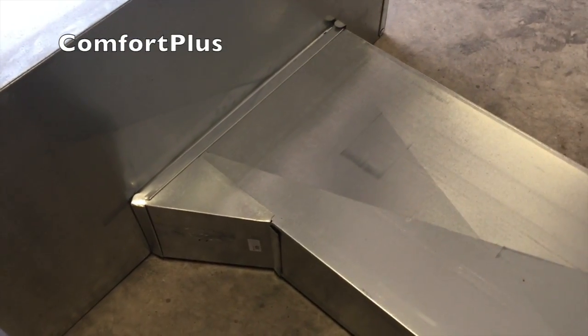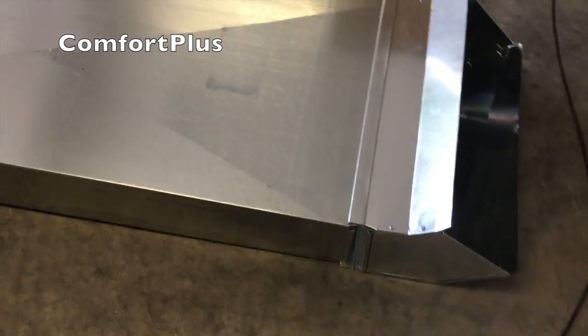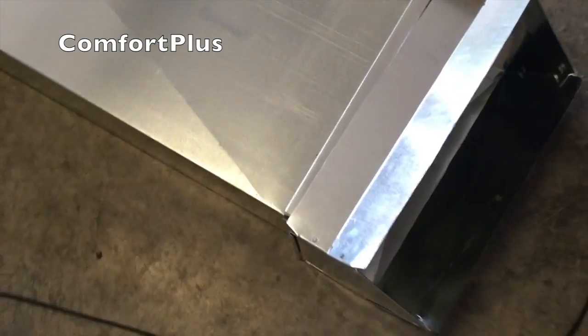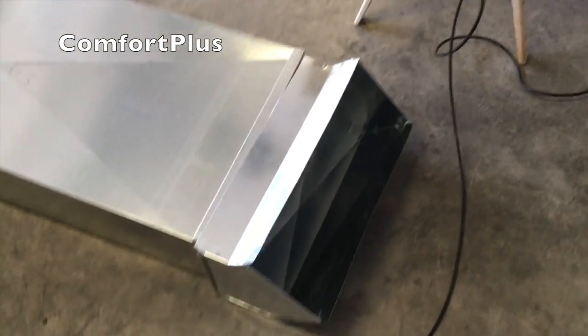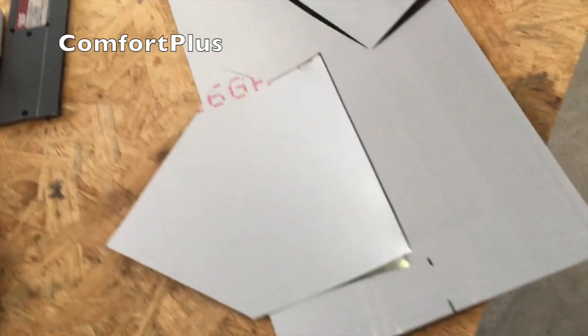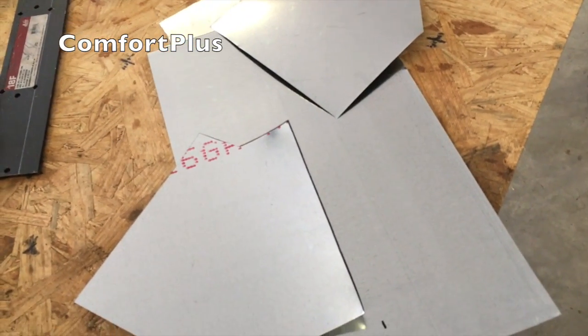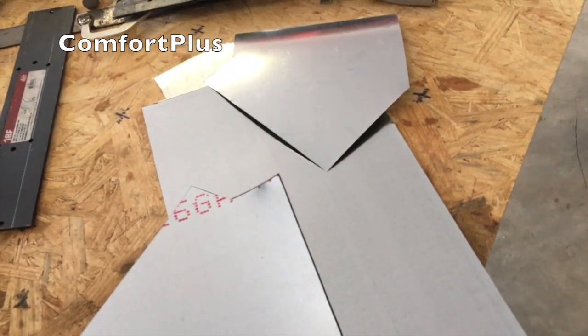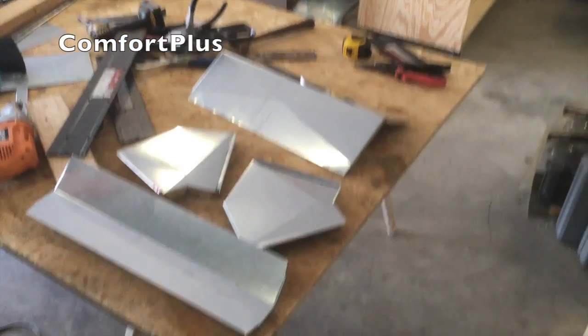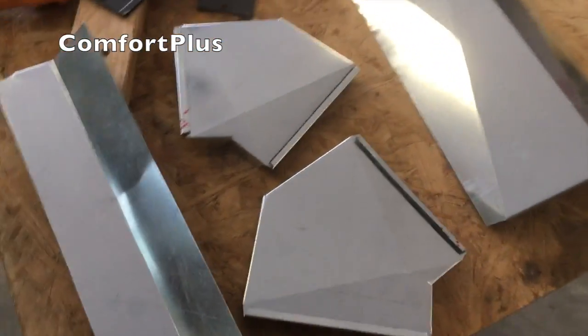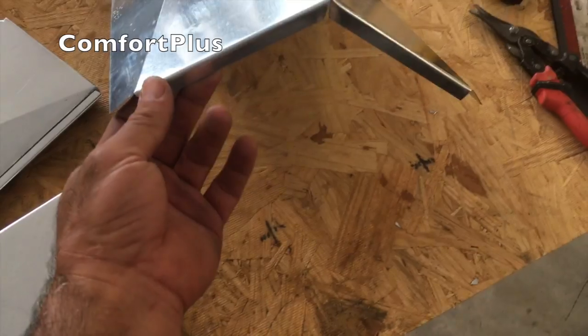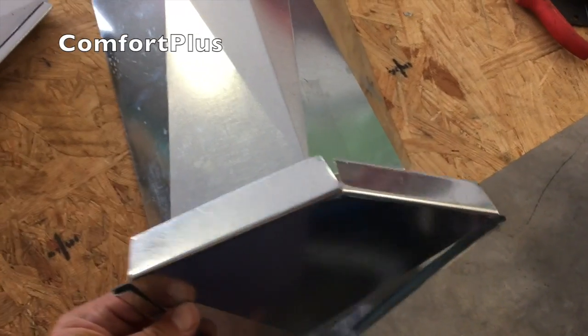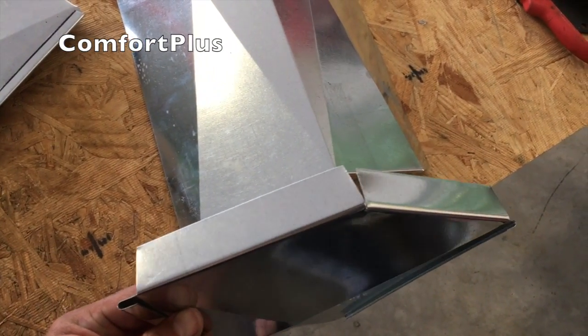Okay, once I come out from under the beam, I'm going to need to get back up underneath the floor joist. The way I'm going to do that is with a 45 transition. The only thing my supply house has are hard 90 fittings. So what I've done is just cut out some pieces here. I've got to make 2 of these, so I will get these prepped to put together and show you what they look like then. And here we have the individual pieces made up, ready to put together. I don't have a Pittsburgh machine or anything, so I basically clamp this stuff together and run screws in it and then seal everything with mastic.